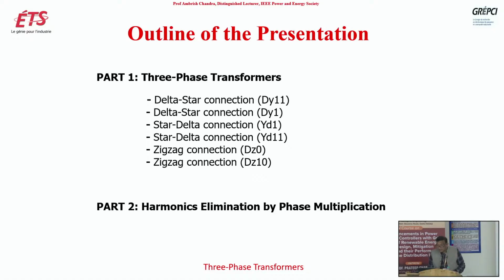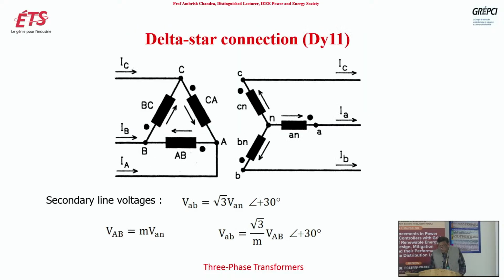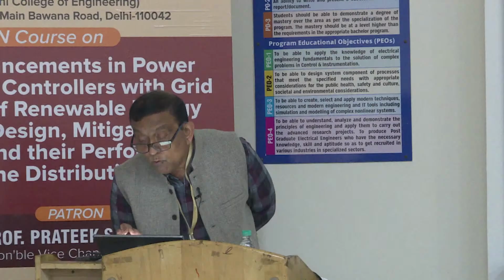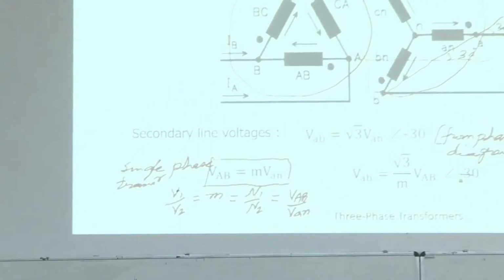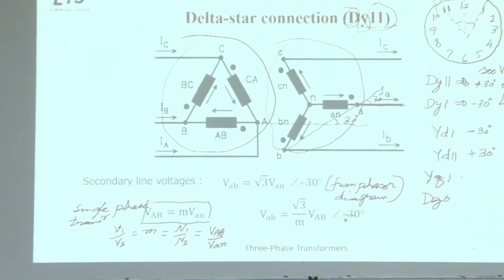So see, if you have this three-phase transformer, if we say DY11, what does it mean? Capital D means on the primary side it is delta connection. Y is in small letters, and small letters mean the secondary side. So the secondary side is star connection or Y connection. Now what does 11 mean? 11 specifies the phase shift it will give, right?